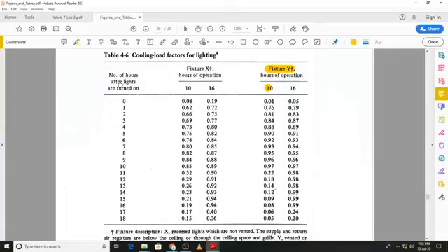And in the first column we have number of hours after lights are turned on, and this value is again worked out similar to the value that we had used in the case of occupancy, that is how much time has elapsed since the lights were switched on until the time you are finding out the cooling load. So we start from 800 hours when the lights are switched on, and we are finding out the cooling load at 1400 hours, so 6 hours have passed until then.